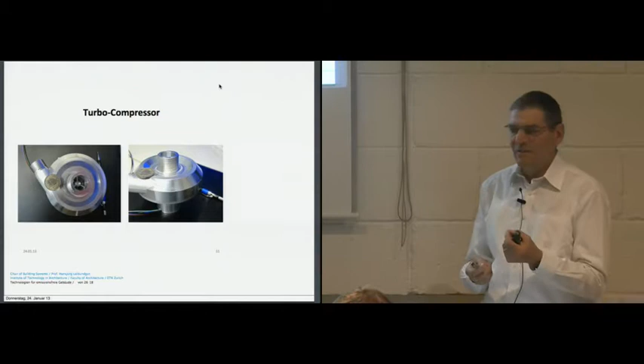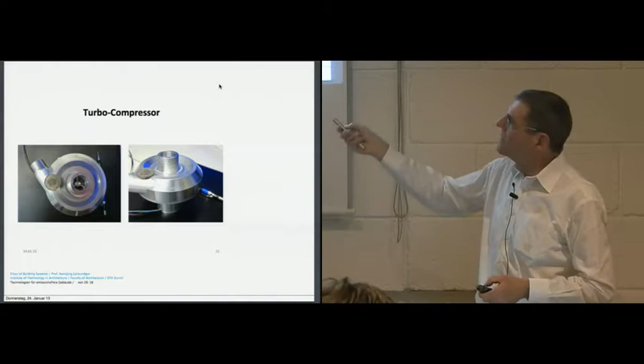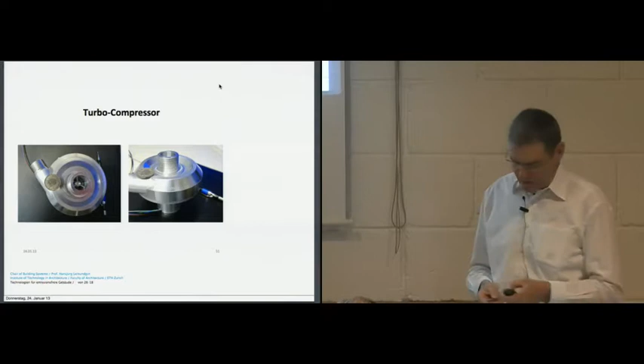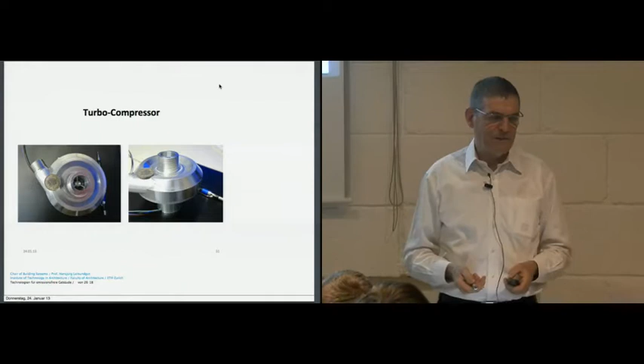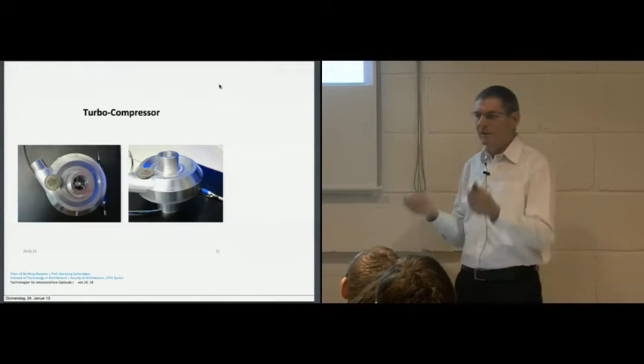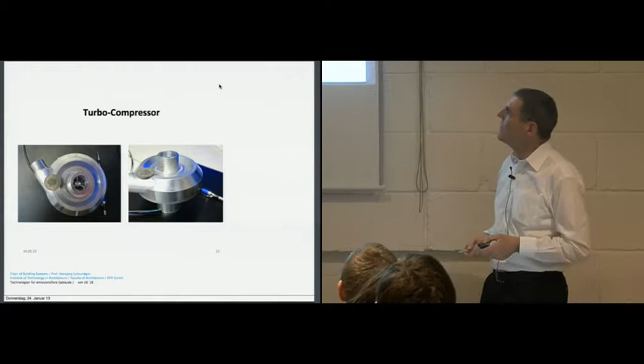So our problem was a small turbo machine. And a small turbo machine needs a very high speed of the impeller. So that is now the prototype. This picture was taken 2 years ago. That is the size, and that is a compressor of 10 kilowatt of thermal power. If we go up to 15, which corresponds to one earth probe of 450 meters, it will be a little bit bigger, let's say 10% more in diameter. This machine is turning with a speed of 148,000 revolutions a minute. Again, it was not possible to have electrical motors with such high speed. That is a thing of the new electrical systems. It was not possible 5 or 10 years ago. This is a spin-off company of the ETH, and they produce motors with 1 million revolutions a minute.